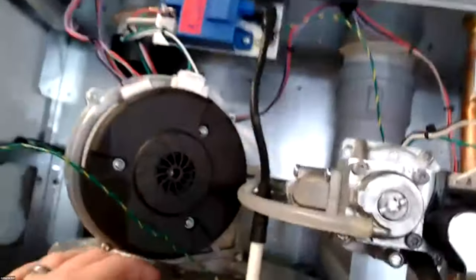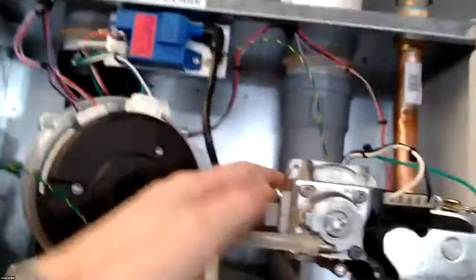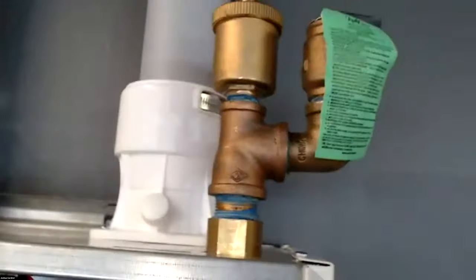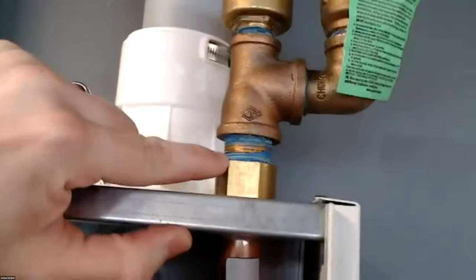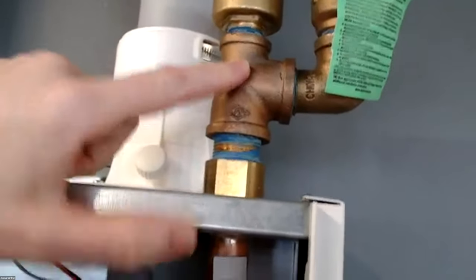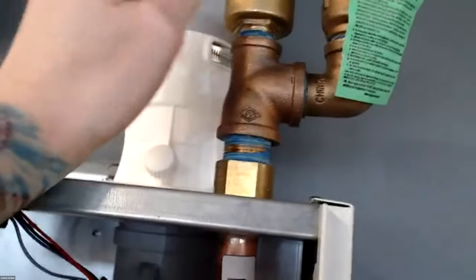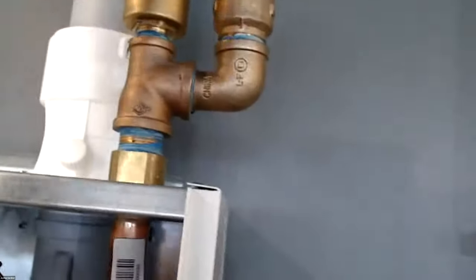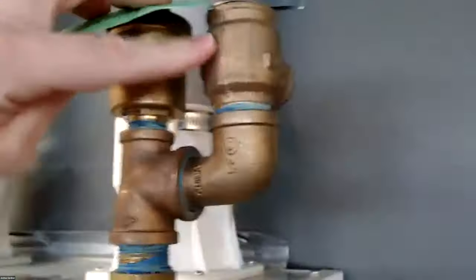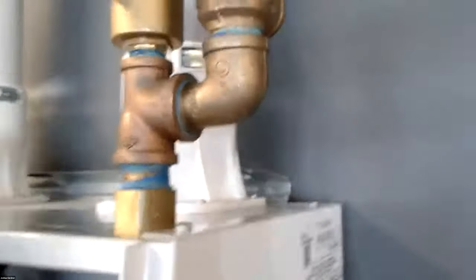Then our fan comes down, goes into our burner top. The gas line comes over into our gas valve, which then goes down into the gas valve connection. Our exhaust tube is right over on here. It's our exhaust line. And then again, the fittings that come with it, you'll get a nipple, you'll get a T, your hi-vent, Caleffi, will thread into right here, and then you'll have a 90, street 90, and then your relief valve, which you can pipe off the side of the boiler.